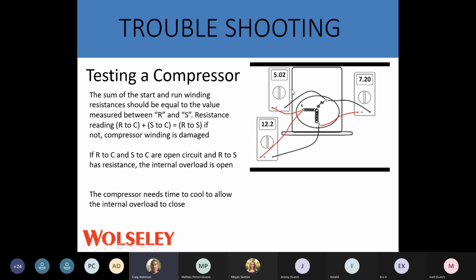It might say OL, you're not getting any reading, then we know right away that there's something going on. We should have resistance between those windings, and they should add up to your R to S. If they don't, then we have some winding damage. If your R to your C or your S to your C are open circuits, and your R to your S has resistance, then you have an internal overload that's open in the system.